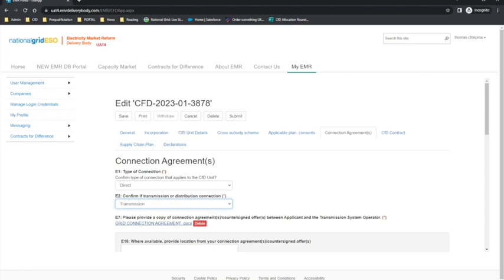There are a number of validation checks that the delivery body will perform on the uploaded documentation. In this direct transmission example, these include: firstly, that the transmission entry capacity specified in the connection agreement is at least 75% of the initial installed capacity estimate of the CFD unit; next, that the target commissioning date appears to be on or after the connection date specified in the connection agreement; and that there is nothing in the connection agreement indicating that the technology of the CFD unit is not the same as specified in the application form.